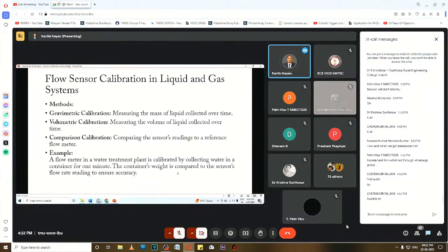Next one is flow sensor calibration in liquid and gas systems. There are three types of calibration used: gravimetric calibration, volumetric calibration, and comparison calibration. First one is gravimetric calibration, measuring the mass of liquid collected over time. So we measure how much mass there is, and it has to be calculated according to the time. Next one is volumetric calibration, measuring the volume of liquid collected over time.